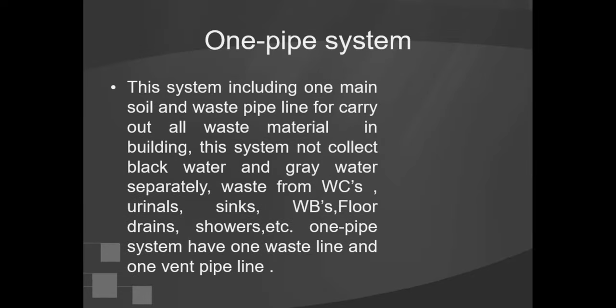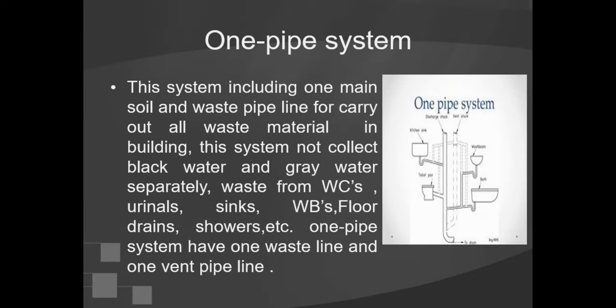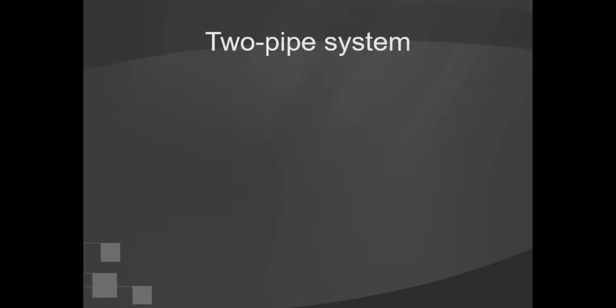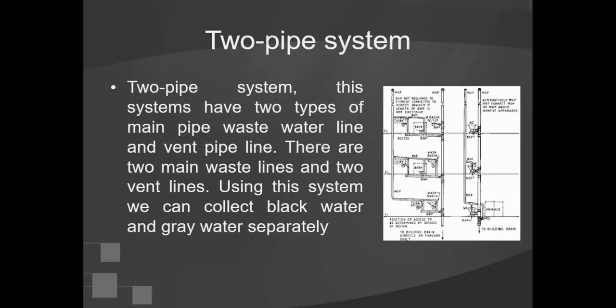The one pipe system includes one main soil and waste pipeline to carry out all waste material in the building. This system does not collect black water and grey water separately — waste from WCs, urinals, sinks, wash basins, floor drains, showers, etc. all goes together. It has one waste line and one vent pipe line. The two pipe system has two types of main pipes: waste water line and vent pipe line, with two main waste lines and two vent lines, allowing black water and grey water to be collected separately.